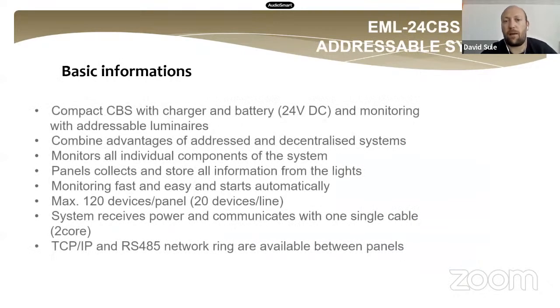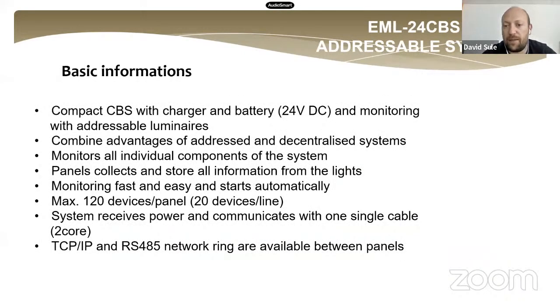So the basic information: this 24-volt DC central battery system is a compact system with a built-in charger and 2 or 4 batteries inside. The 2 batteries connected to each other give the 24 volts when the AC is missing from the system. This system can have 1 hour backup time or 3 hour backup time. The 1 hour backup time contains 2 batteries inside, and for the 3 hour backup time, 4 batteries are installed in the panel box.